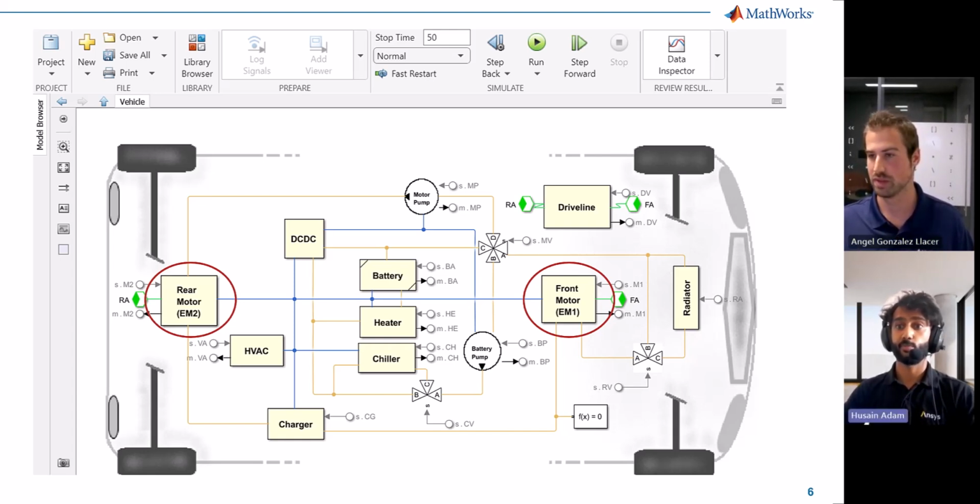Yeah, that's right. So the MotorCAD model focuses on the thermal performance of simply the electric machine, but many of our users then want to use this detail model and integrate it into the larger system, such as what you're showing here. So that the larger system which contains the motor, but also the power electronics and the battery pack. And then the cooling of the motor is then integrated with the coolant, flowing through all of these different elements, and that can be done in a smart way that improves the overall system efficiency.